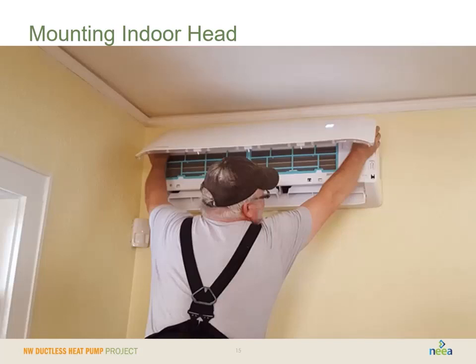And here we have someone actually mounting a ductless heat pump head. The indoor head mounts and secures directly to that bracket. What you're not seeing here is, some holes had to be drilled in the building beforehand, and the electrical and the refrigerant run through, but this is what it looks like mounting that indoor head.